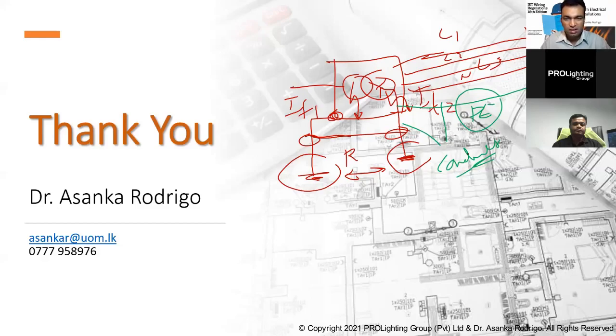No problem. The first one is, can we use 1.5 square millimeter cable with a 10 ampere MCB for a 13 ampere socket? No, as per the standard, when you look at these main distributions, you have to have 20 ampere and 30 ampere. But if you have spur lines, you can use the 1.5 square millimeter, there is no harm. But you are restricted, because in the IET wiring regulations, earlier certain diversity factors were defined for your calculation. When you look at this 13 ampere socket outlet, if you are using only one 13 ampere socket outlet, then this 1.5 square millimeter is sufficient for the maximum demand.